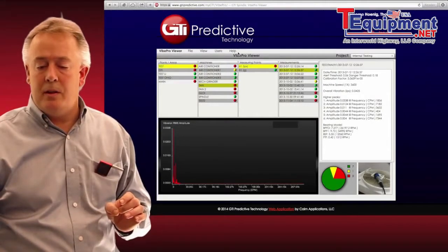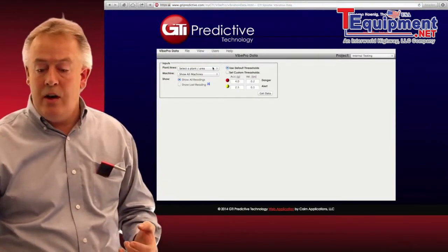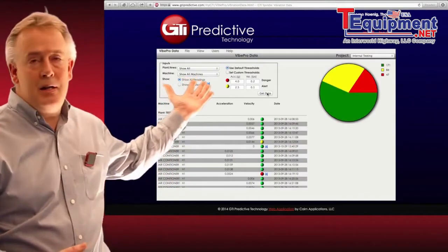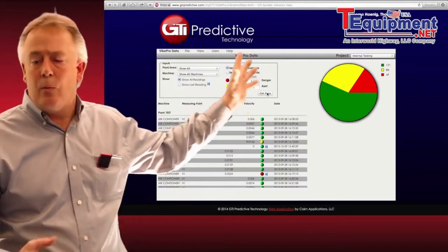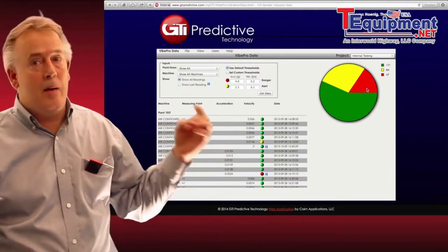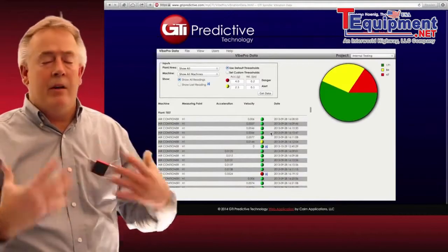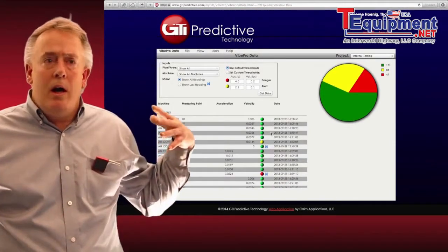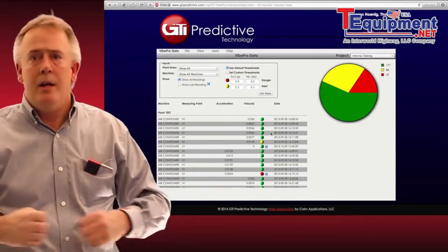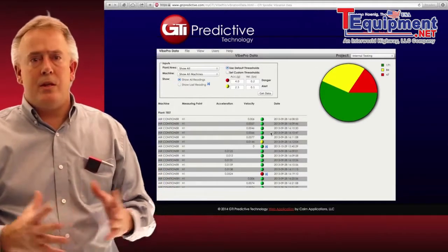Pulling the spectrum back down, we go to the view button and select vibration data. This lets us select all the plants, all the areas within our plant, or specific asset points, hit show all, and then click get data. It pulls down a nice report of the whole entire factory or plant — showing how many asset points are in the yellow, how many are in the red, how many are in the green — and we can drill down on any of those. There's no heavy lifting: you simply beam up the data to the web app, click get data, and print out those reports for your superiors.